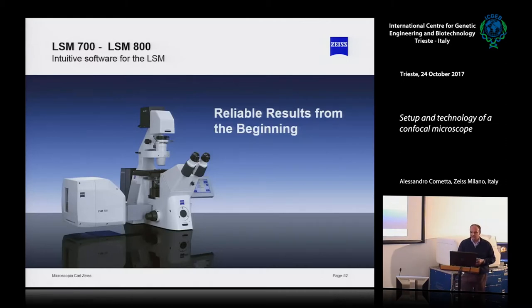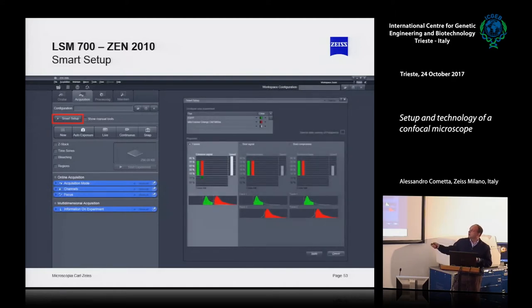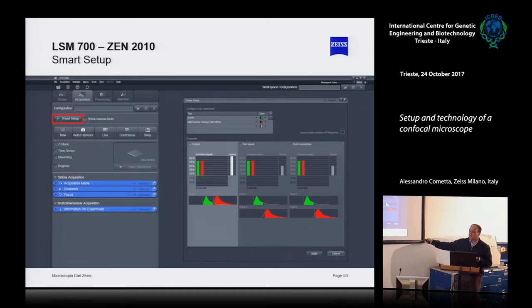On the software side, starting from the very beginning of the new spectral microscopes, a simple software has been introduced to help you manage all these filters. This is very important when you set up your microscope, even if you don't use this kind of software, because you have to understand that you can acquire on a single track simultaneously or in two different tracks. Usually the preferred way is to acquire one color and then the other, in sequential tracks.